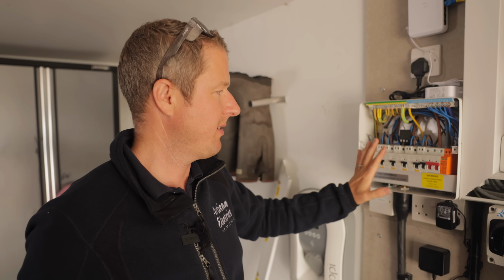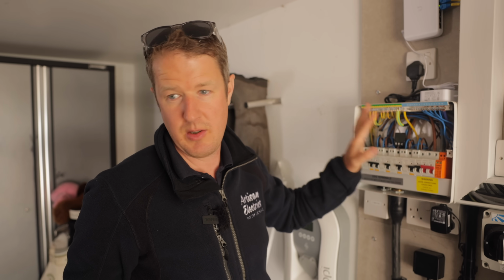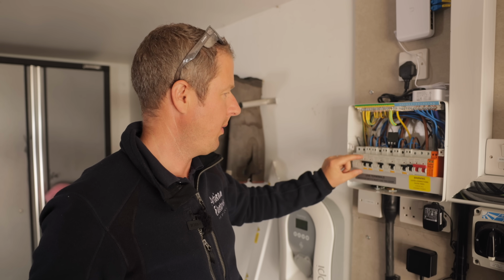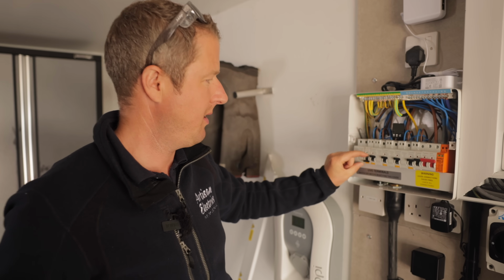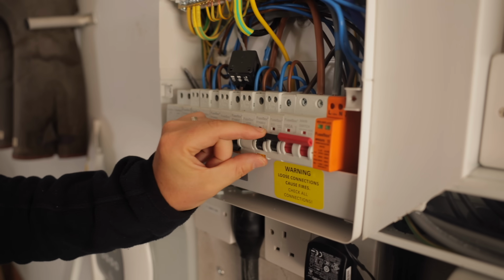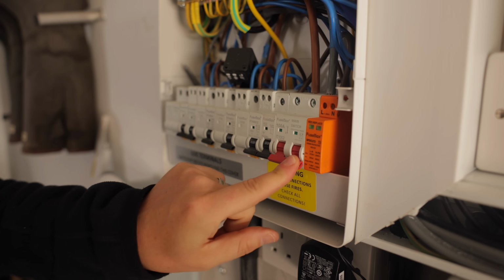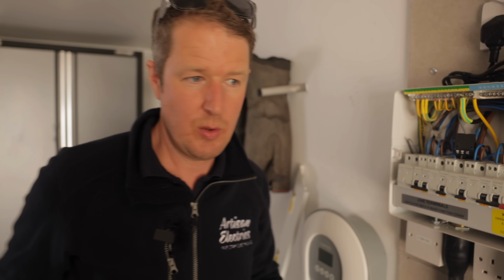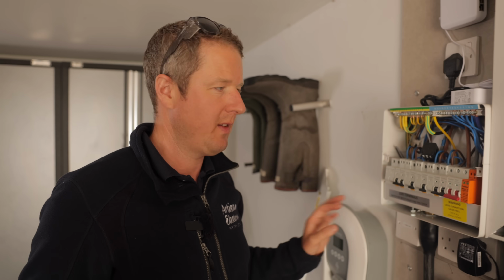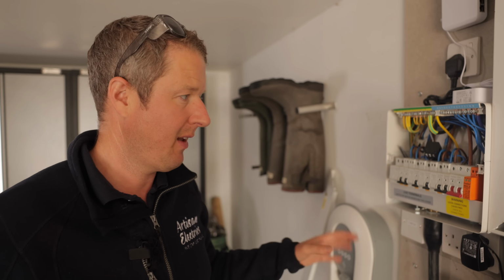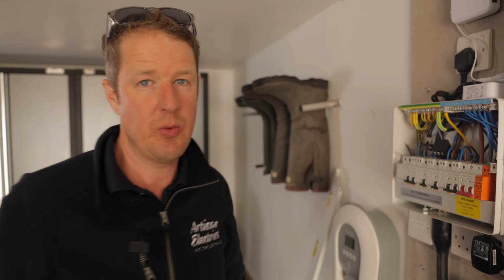So now as we're about to start working in the consumer unit, we need to make sure everything's safely isolated. So we're going to just turn off all the circuit breakers in here for the moment, and then turn off the main switch, and then we'll just do a test to make sure it's all dead. Whenever you're working on electrics, always make sure you isolate safely, and if there's other people around, lock out, tag out as well.